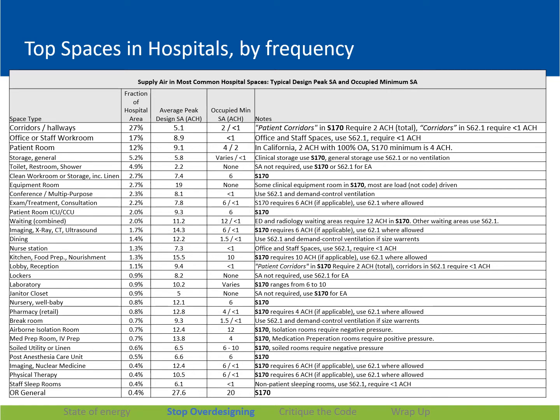In third place is patient rooms. Our average design engineer put in a peak of 9 air changes in our patient rooms. Under code, the minimum is 4 air changes almost anywhere you go, sometimes lower, which is at least a 65% turndown opportunity. The second most common spaces in the hospitals is administrative areas. 20% of hospital buildings are administrative spaces. And our design engineers have been putting in, again, 9 air changes in those spaces. Well, that's a lot of air. We can do a 90% turn down there under any code scenario that I know within the country.